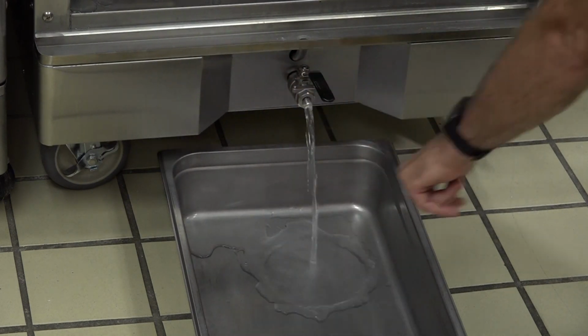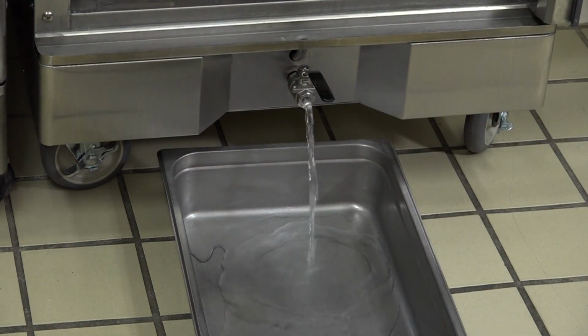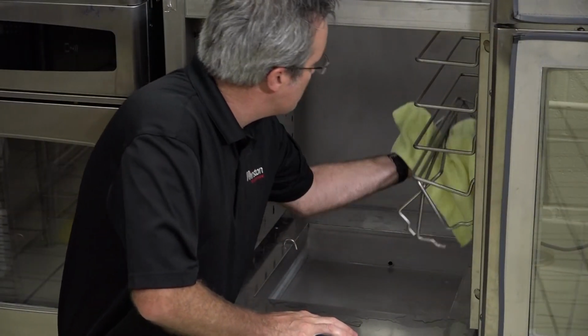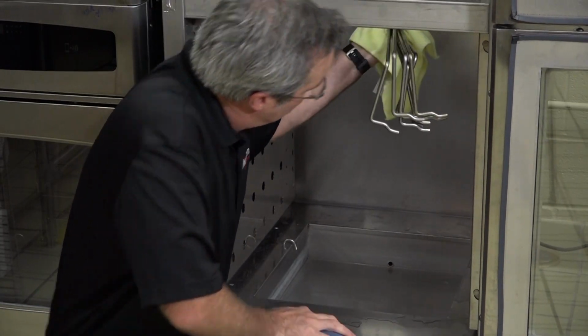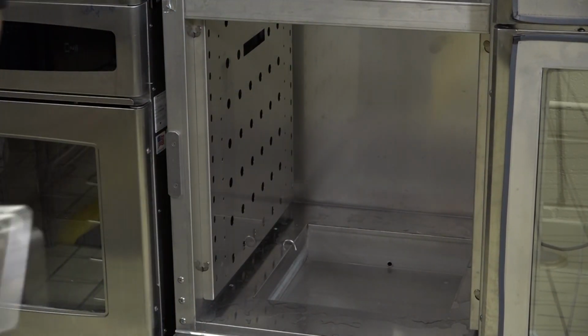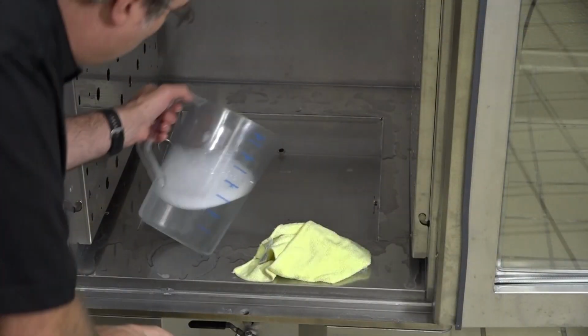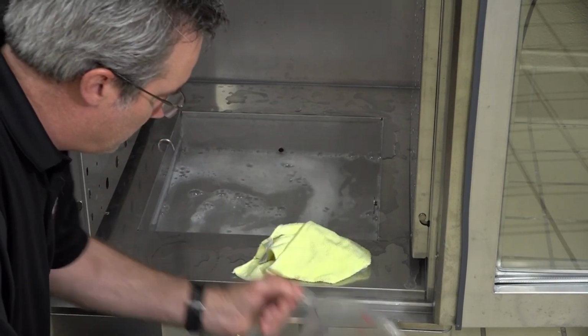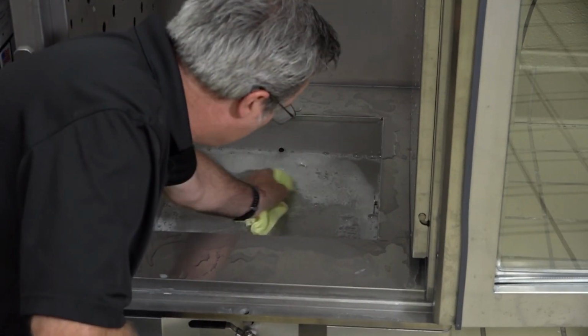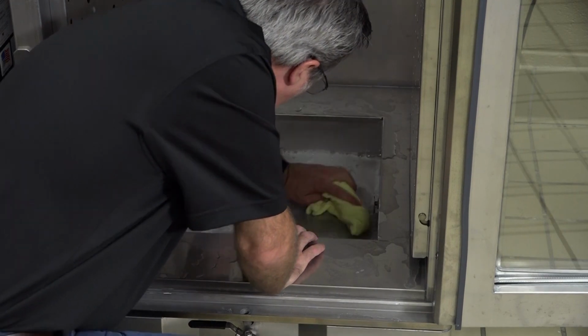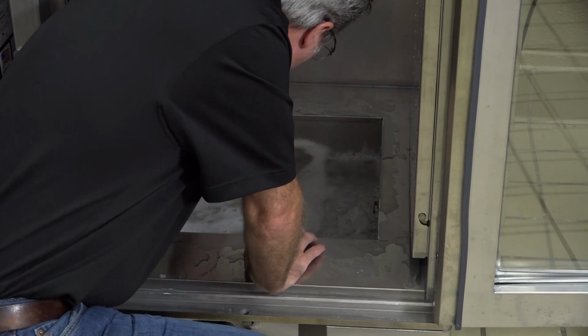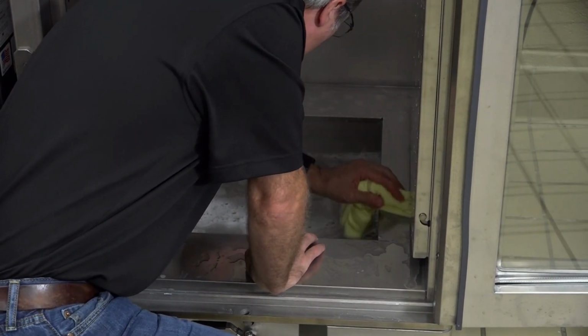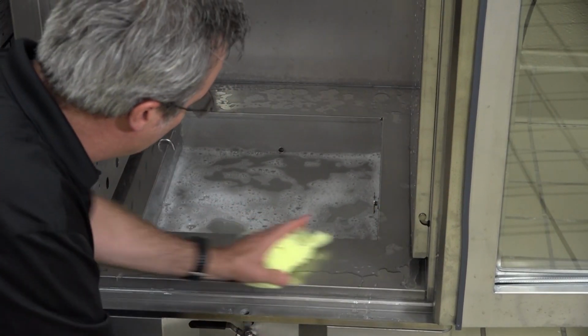Place an empty bucket or pan under the drain valve. Open the drain valve and allow the evaporator to drain. Remove and clean rack supports using a food-grade stainless steel safe detergent. Spray or wipe the food chamber and evaporator with a food-grade stainless steel safe detergent. Wipe the inside surface to remove all food deposits.